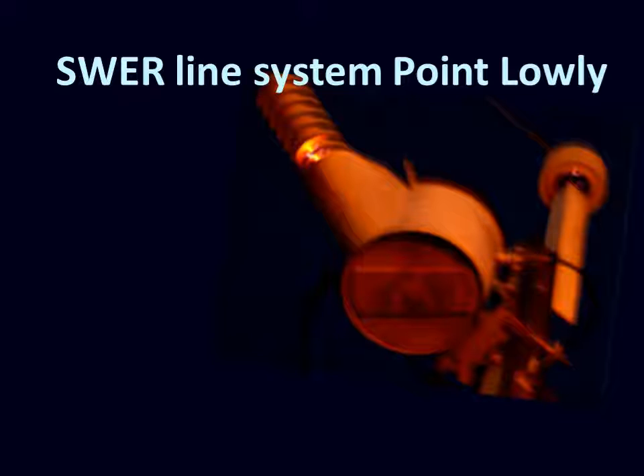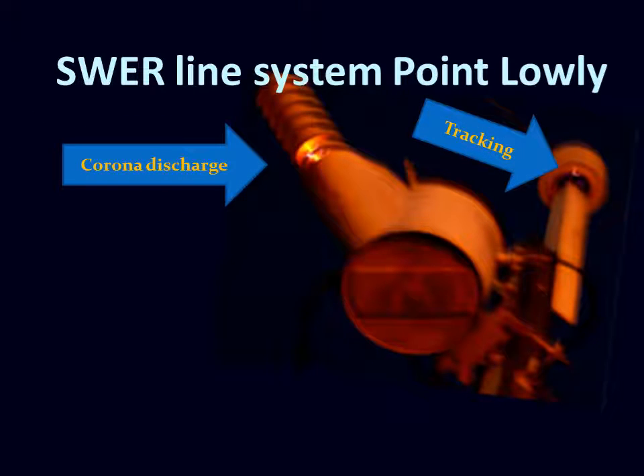Pictured is a SWER line transformer at Point Lowly in South Australia. The transformer has a feed-in voltage of 19 kilovolts and supplies a number of domestic dwellings at 230 volts. Note the discharge and tracking associated with the environmental conditions. Adding transformers also adds loss, with transformers being less than 100% efficient, but it may also add flexibility with auto-tap changing, enabling some compensation for changing loads.